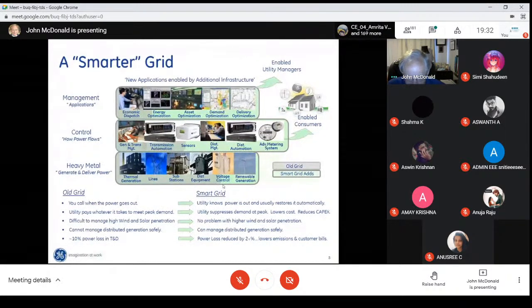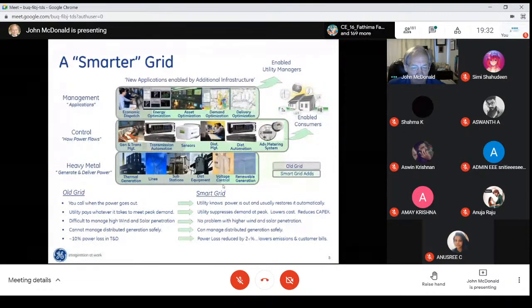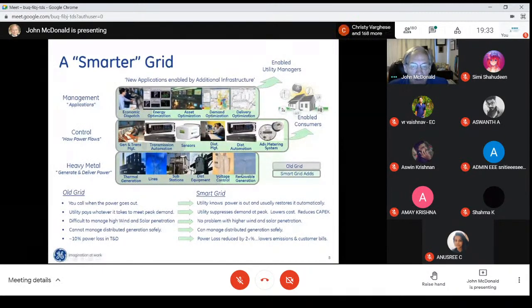In addition, to reduce losses, we would control reactive power with capacitor banks and voltage regulators, and that was called VAR control, reactive power control. And for many years, we did these separately. So what the light green part of this shows is that we're now doing voltage control and reactive power control together. We call that integrated volt-VAR control, or volt-VAR optimization, okay? We'll talk more about renewable generation.